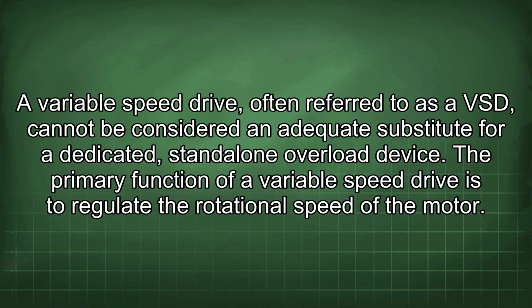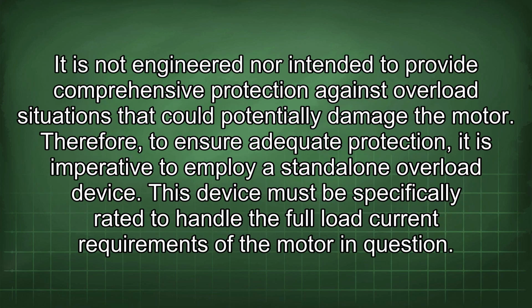A variable speed drive, often referred to as a VSD, cannot be considered an adequate substitute for a dedicated, standalone overload device. The primary function of a variable speed drive is to regulate the rotational speed of the motor. It is not engineered nor intended to provide comprehensive protection against overload situations that could potentially damage the motor. Therefore, to ensure adequate protection, it is imperative to employ a standalone overload device.